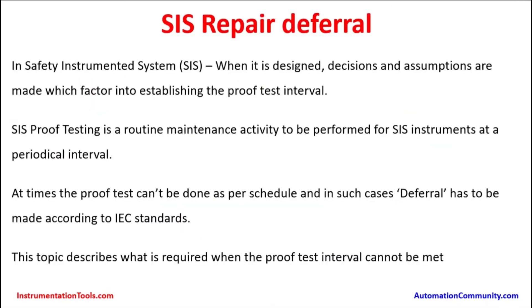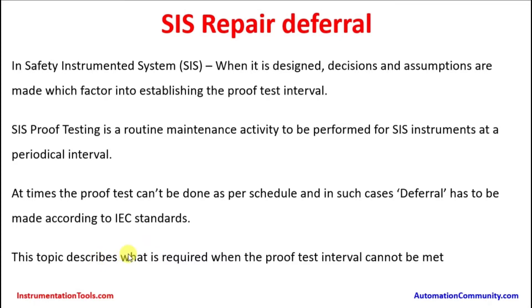SIS repair deferral — in a safety instrumented system, decisions and assumptions are made which factor into establishing the proof test interval. SIS proof testing is a routine maintenance activity performed for SIS instruments at a periodic interval. At times the proof tests cannot be done as per schedule, and in such cases deferral has to be made according to the IEC (International Electro-Technical Commission) standards. This topic describes what is required when proof test intervals cannot be met.